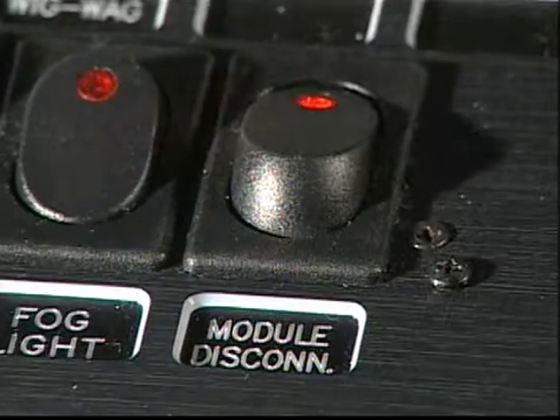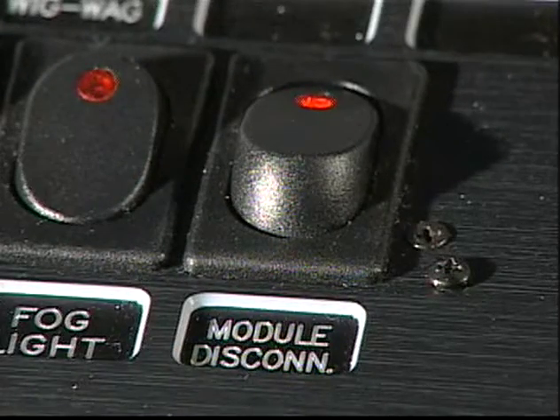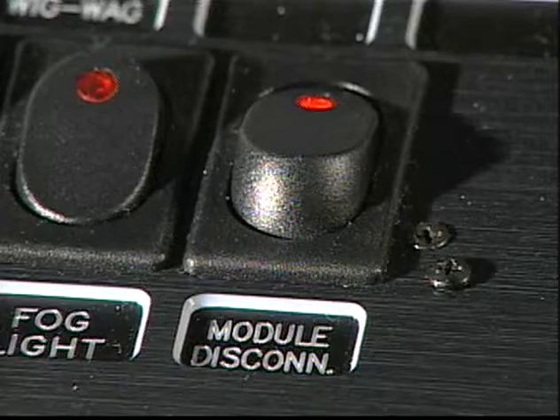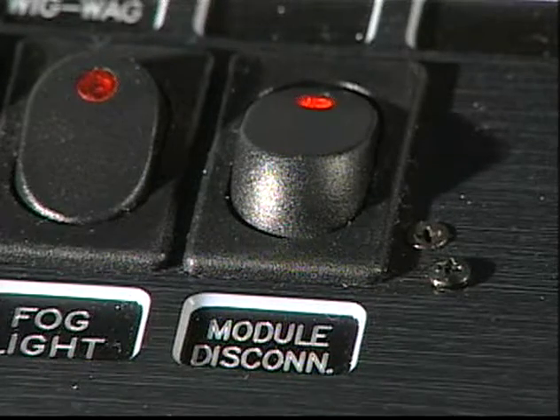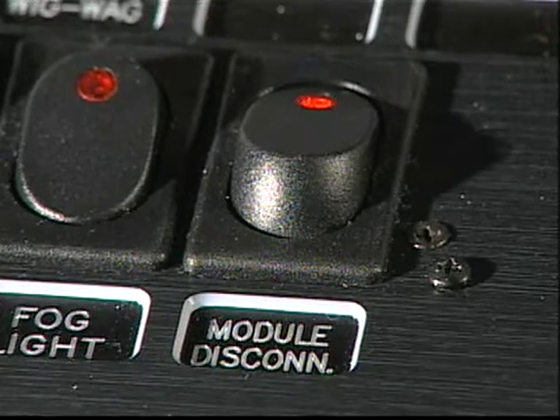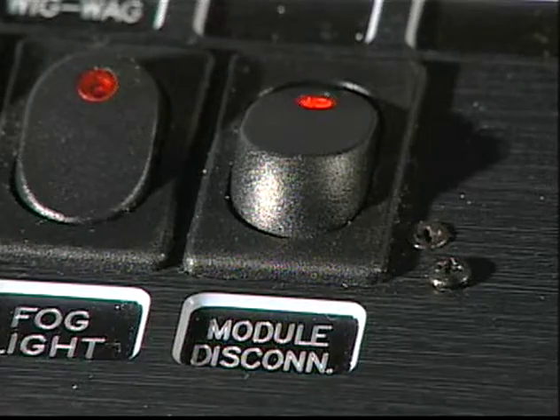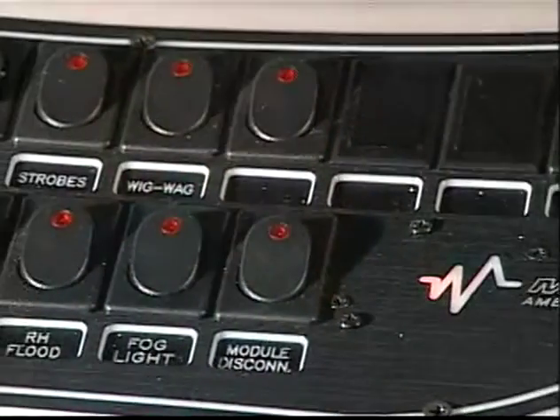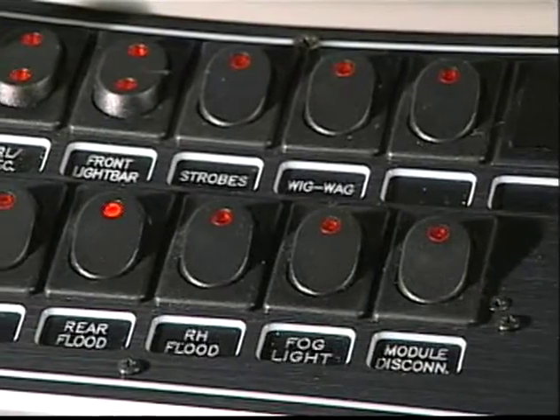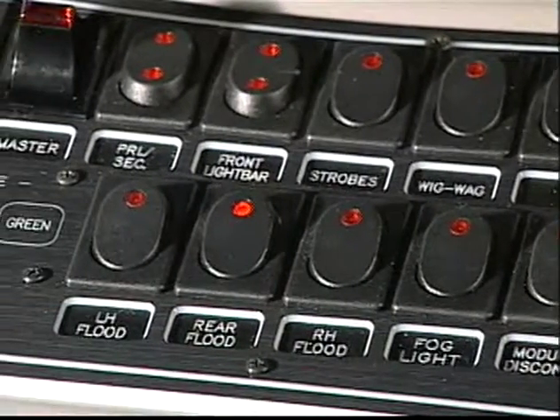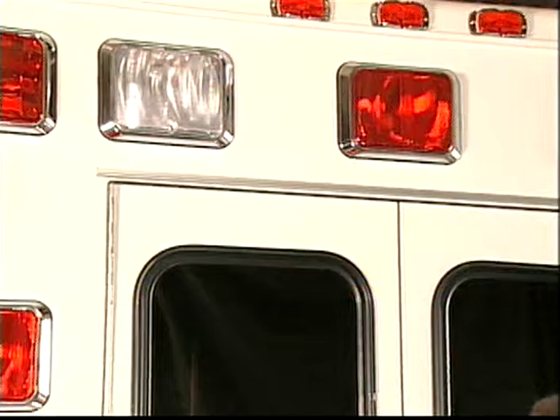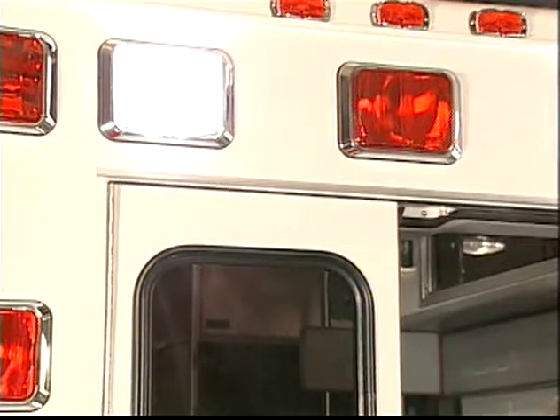The module disconnect switch controls the 12-volt DC power to the patient compartment. This switch must be on to operate the equipment controlled by the rear electrical control panel. The other switches on the front console switch panel operate the emergency warning equipment as indicated by the switch label, such as floodlights, rear light bar, front light bar, wigwags, air horn, etc. The rear floodlights will turn on automatically when either the rear doors are open or the ambulance is put in reverse.